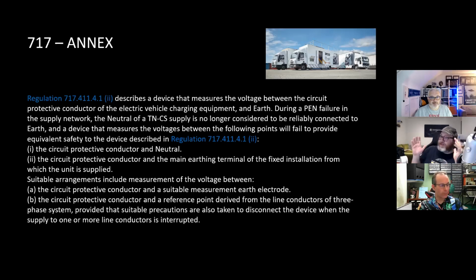What they need to do is go back to 4.1, and go to TN systems in 4.1, and with TN systems, if PME is installed and then you're outside, just have this protection as a standard. Then you haven't got to keep repeating it. Okay, but yeah, it's just describing where the protection works here between the CPC and the neutral situation, or if the CPC and the main earth in terms of the fixed installation has the voltage, and what measurements and protective measures should be taken.